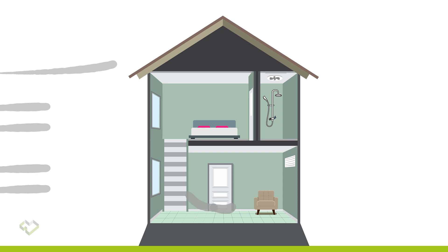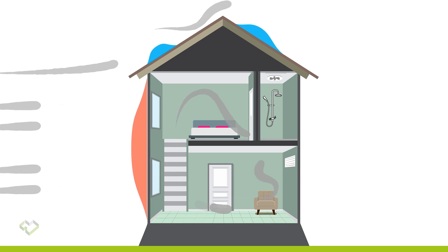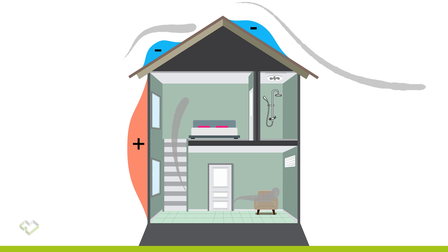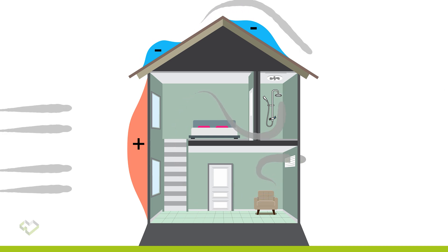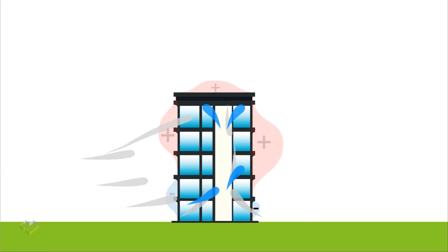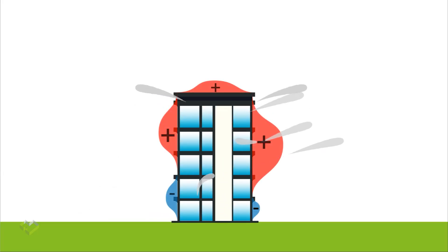When it comes to double storey homes, on the top floor you get faster and cleaner winds acting on the building envelope, and a lot of this air leakage can significantly exacerbate the air moving from the lower floors. The other thing that occurs in double storey homes is a process called stack effect, where the second storey is always warmer than the ground floor. When you combine stack effect and wind effect, this further exacerbates how much energy you'll be paying for heating and cooling your home.